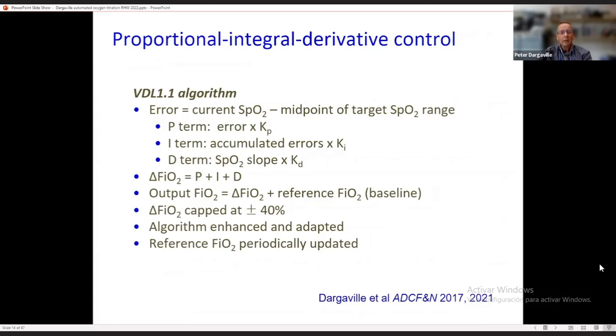Essentially, at every second, every time the algorithm computational loop is iterating, an error is calculated where the midpoint of the SpO2 target range is subtracted from the current SpO2 value to give an error. And then three terms are calculated. The first is the proportional term, which is the error times its coefficient. The second is the integral term, which is the accumulated past errors times its coefficient. And the derivative term is the recent SpO2 slope times its coefficient. And so that's looking at the current, past, and future behaviour of SpO2.